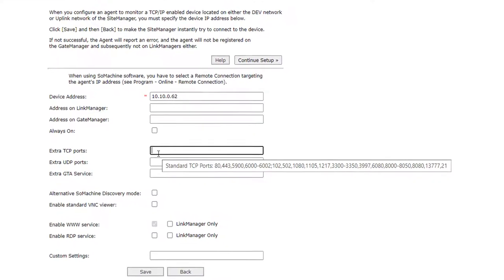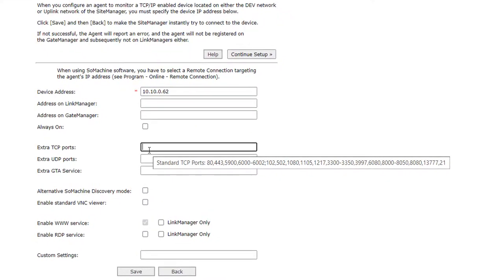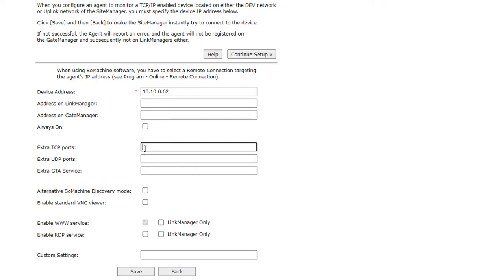For the M262, port 11740 is not opened by default, but it is required to be able to connect to the PLC. You have to add it manually.